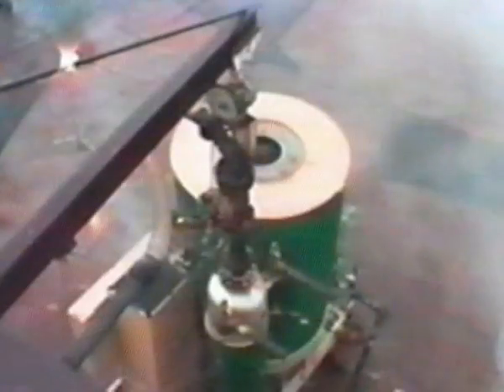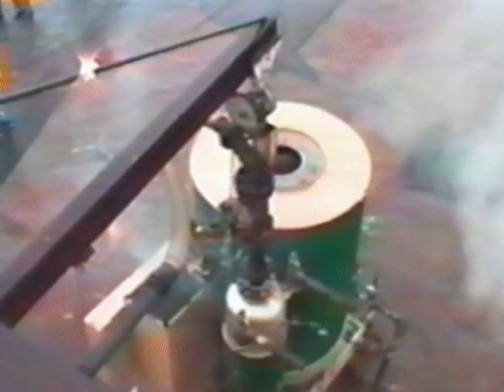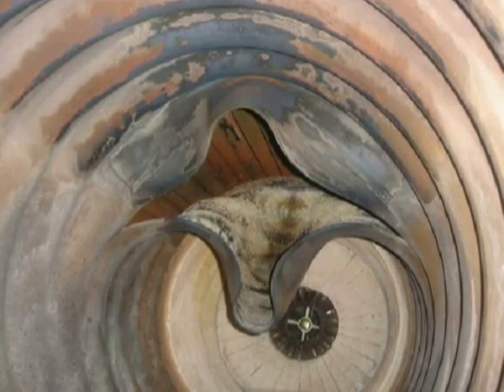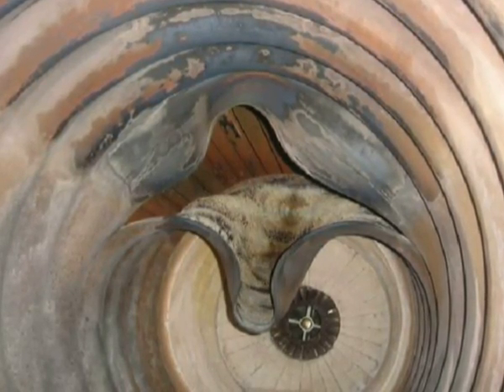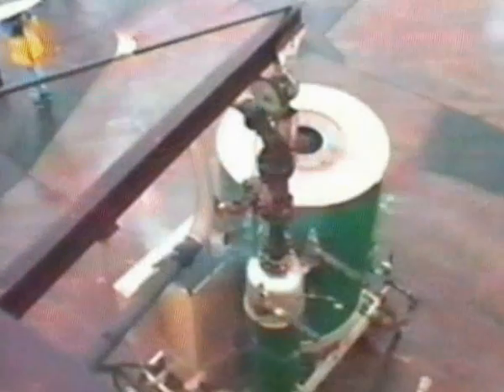What you will see in the next few minutes is the full destruction of the steam generator pressure vessel without any danger from a steam explosion. Although unlikely, traditional boilers occasionally rupture and the resultant release of energy from the pressure vessel can be deadly. By design, the Clayton monotube coil cannot have a catastrophic steam explosion.